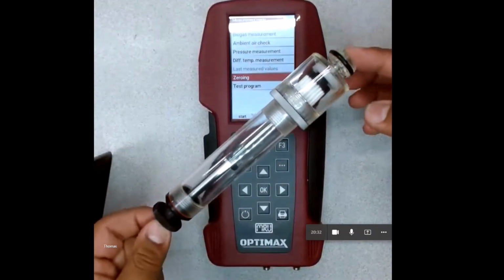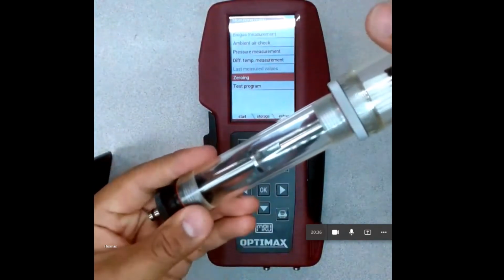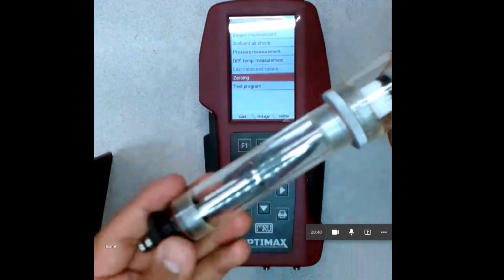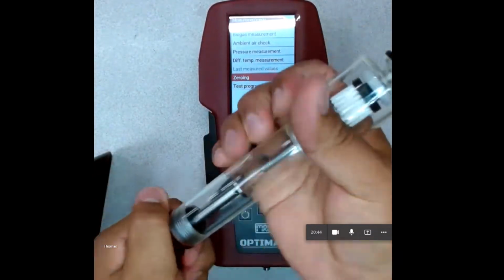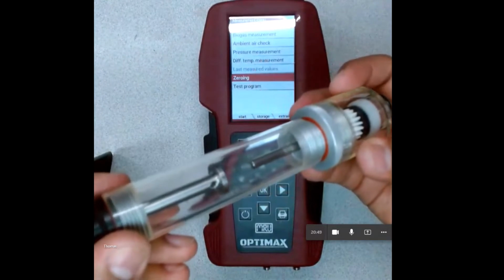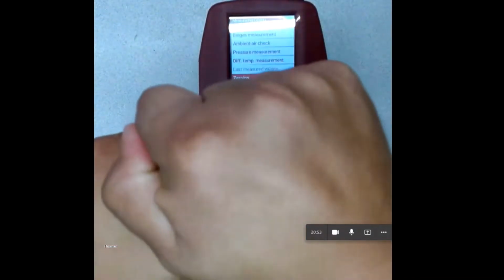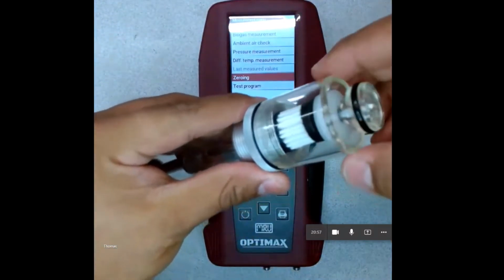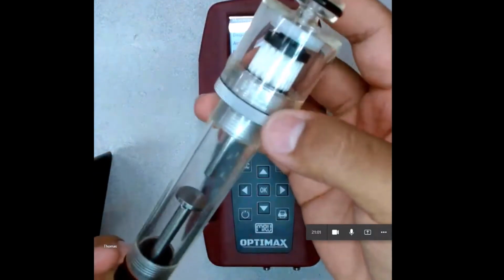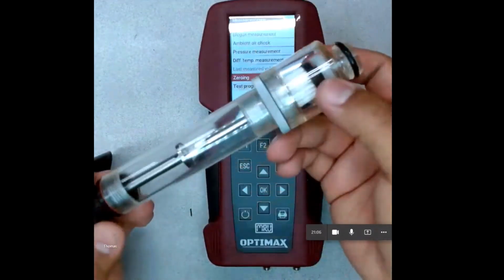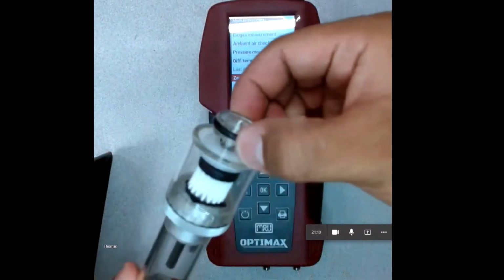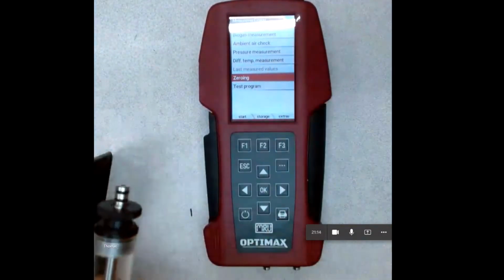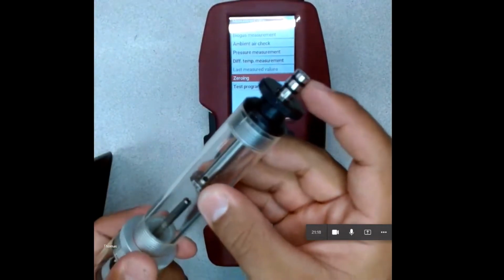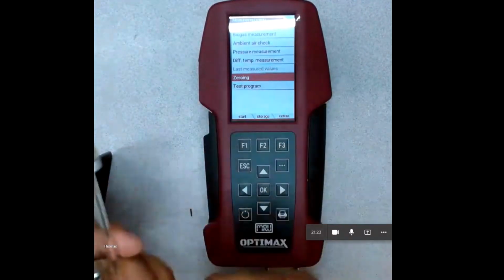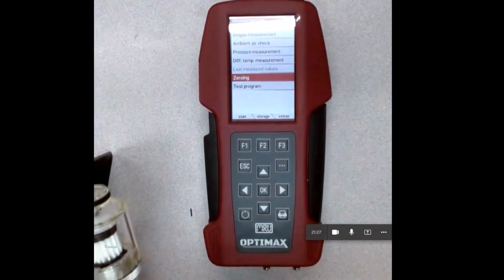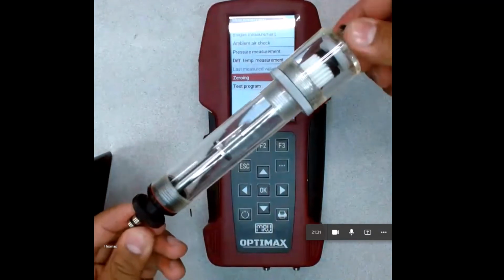The condensate trap for a leak. So that could be that since these are all threaded together, each section of this, if any of these threads are loose, you can have a leak. You can have fresh air coming in. And then also on all of these, there's an O-ring. You see that orange O-ring inside on that part, and then on the top, there's a black O-ring in there. And so if any of the O-rings are cracked, broken, stretched, that can cause a leak as well. The other suspect is this big O-ring on top. This could be damaged. And then also on the bottom, these O-rings right here, two O-rings, these could be damaged as well. So probably with situations that are just the analyzer, about 6 or 7 times out of 10, it'll be something to do with one of these O-rings or threads.